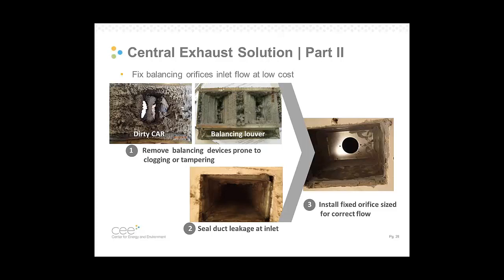At the inlet, in the apartment units, you take off the register and you might find one of these devices. This is a constant air regulator, or a CAR, and this is a balancing louver or balancing damper. The constant air regulator is a self-balancing orifice. What it's designed to do is monitor the pressure in the shaft or in the duct and adjust the opening size according to the pressure.